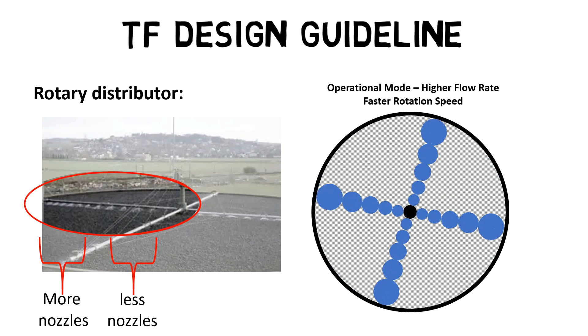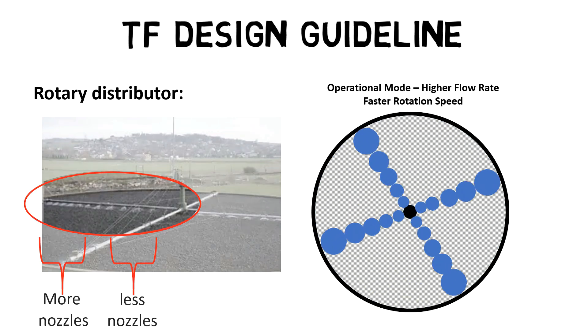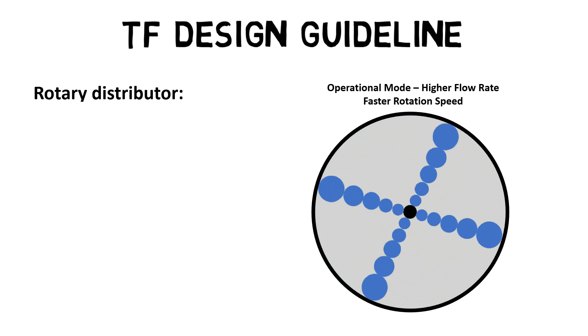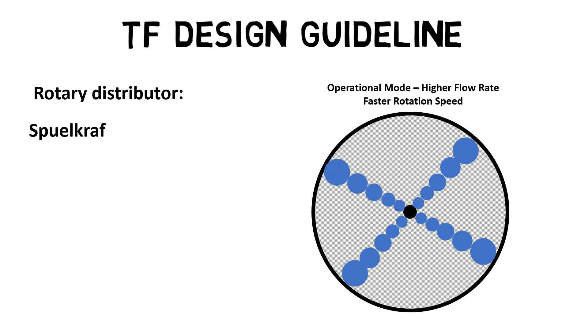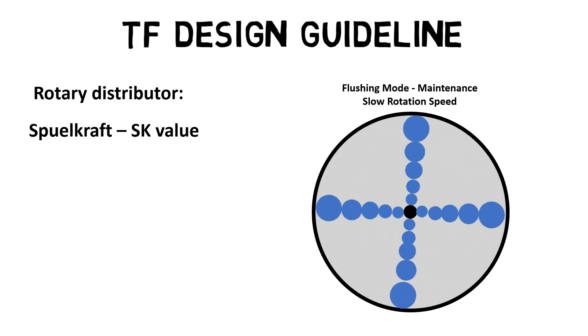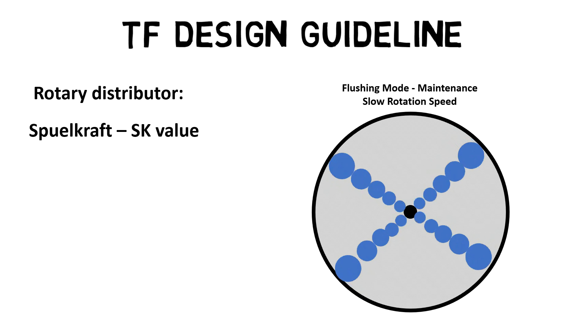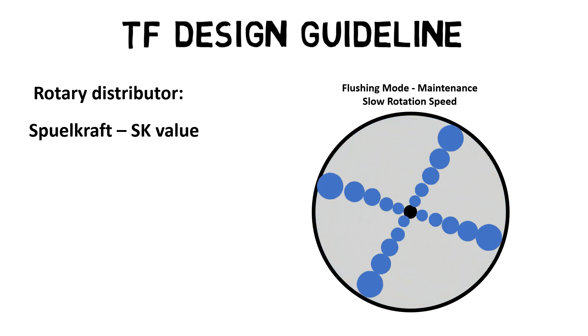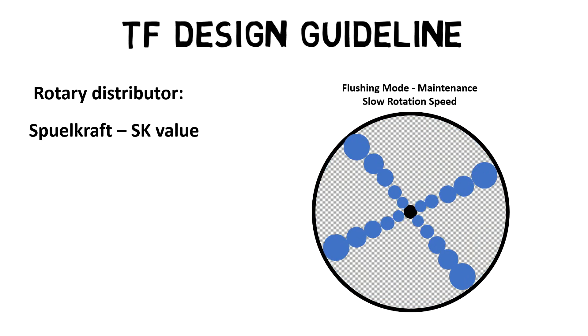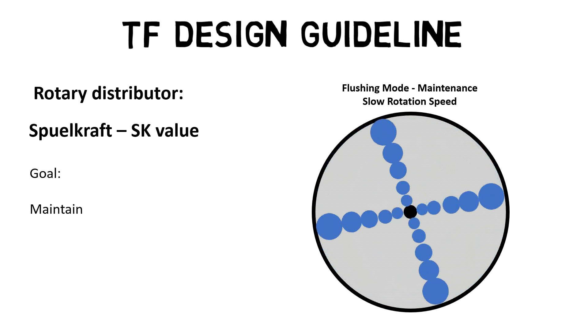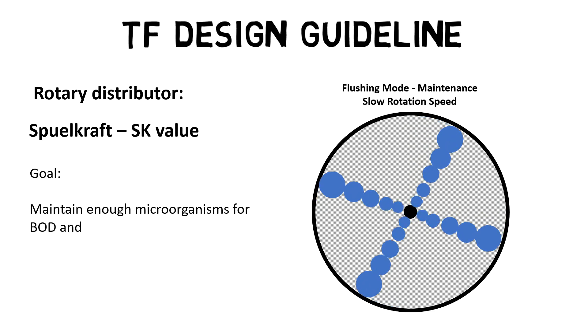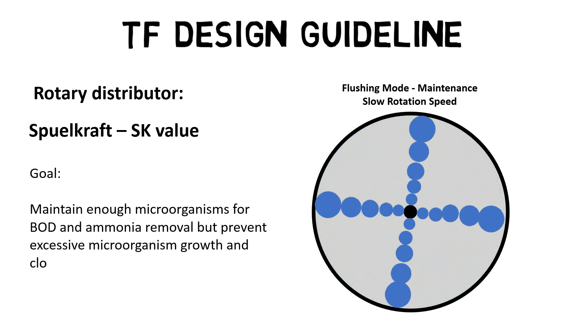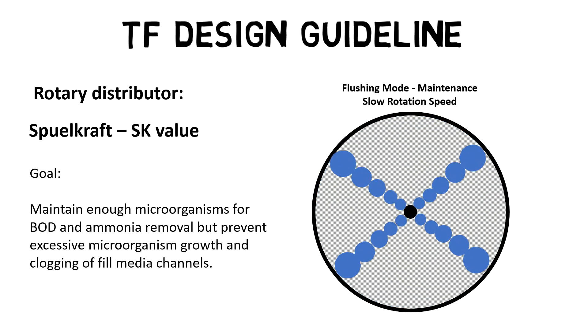The amount of water trickled above a certain plastic-fill media area per minute influences the flushing effect, also known as the Spülkraft or SK value. The higher the SK value, the thinner the layer of microorganisms attached to the plastic-fill media surface. The goal is to maintain enough microorganisms for BOD and ammonia removal, but to prevent excessive microorganism growth and clogging of fill media channels.